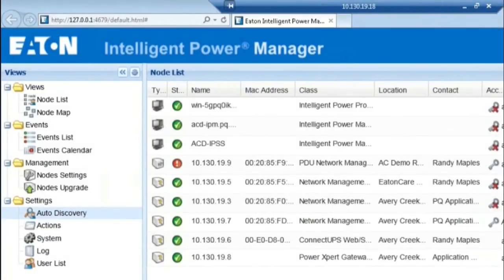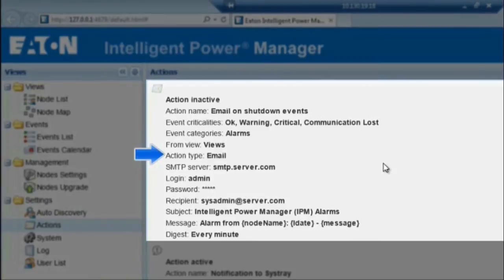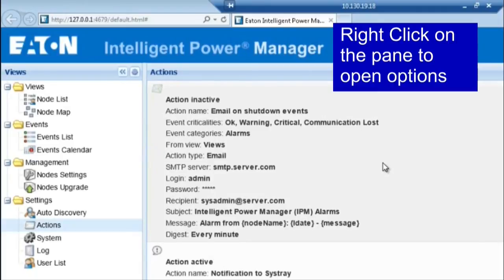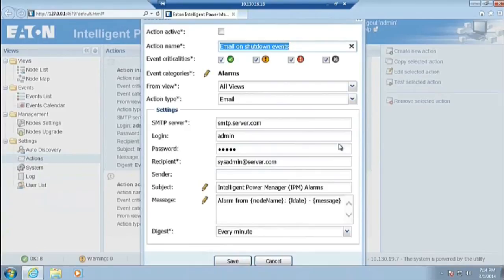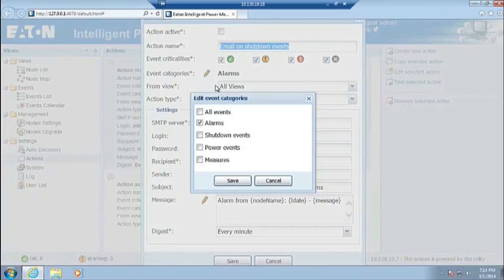We will now set up email alert notifications for warning alarms and critical alarms. First, locate the Views column on the left-hand side of the interface. Next, locate the Settings folder. Then, locate the Actions option. Highlight the pre-configured email action located at the center of the Actions pane. Click on the option Edit Selected Action. At this point, you will be able to configure email notifications to send daily reports detailing warning notifications from the specific day. We will start by selecting the event categories which the generated email will be based on. Click on the pencil icon next to Event Categories. A dialog box will open and provide options for selecting event categories. Click the All Events box and then click Save to continue.